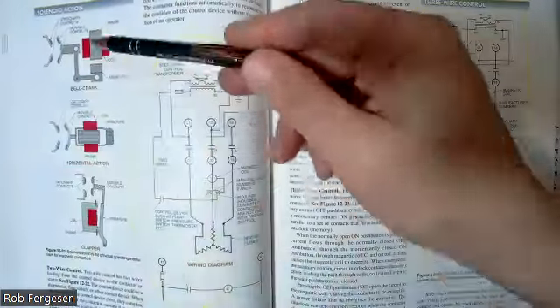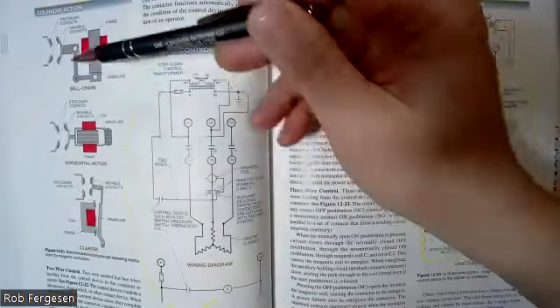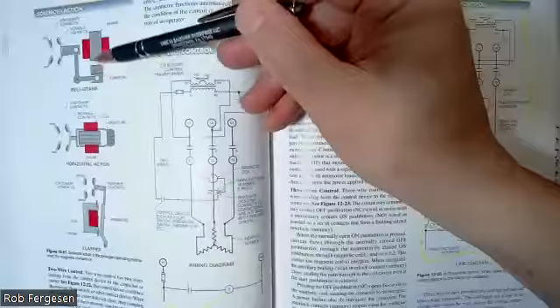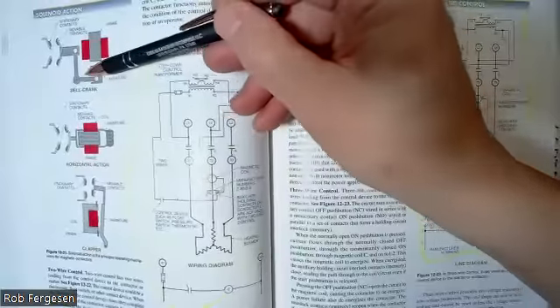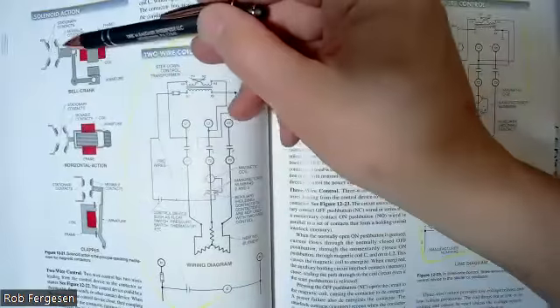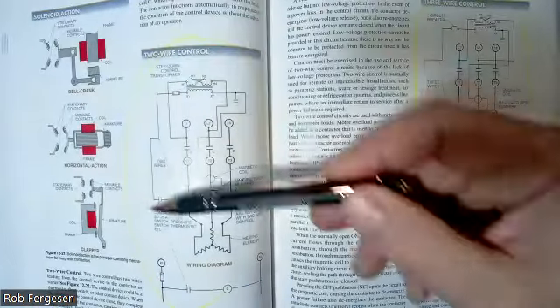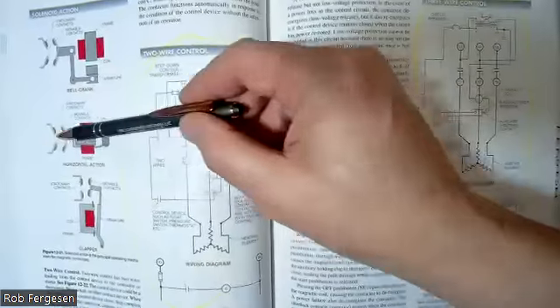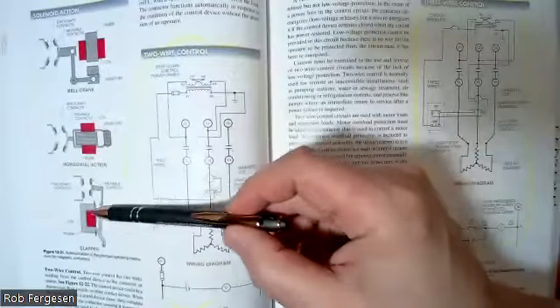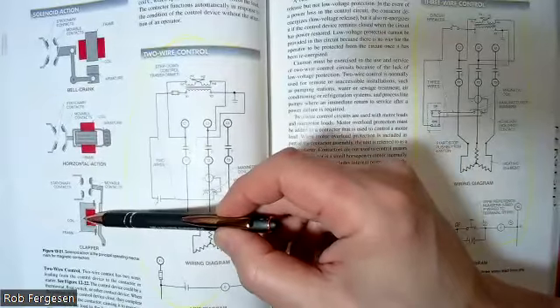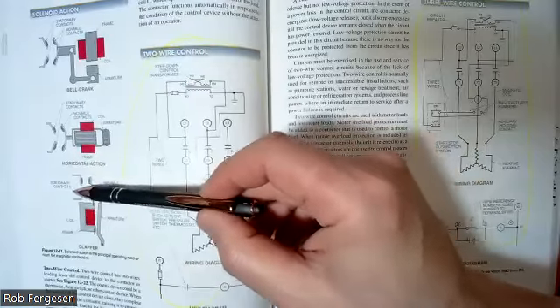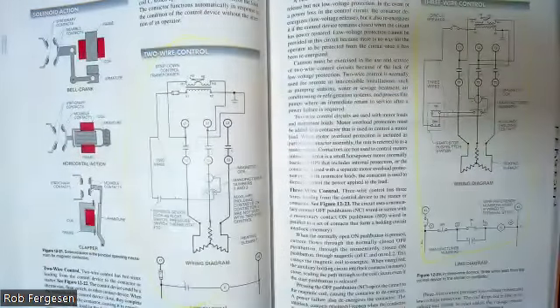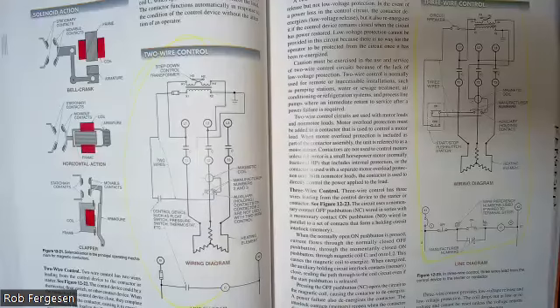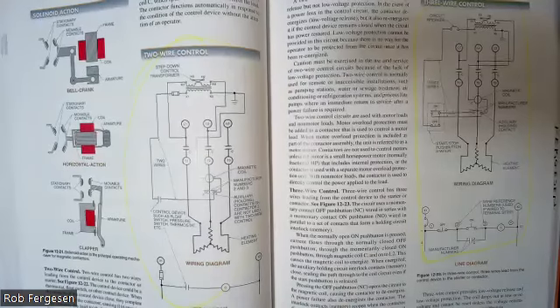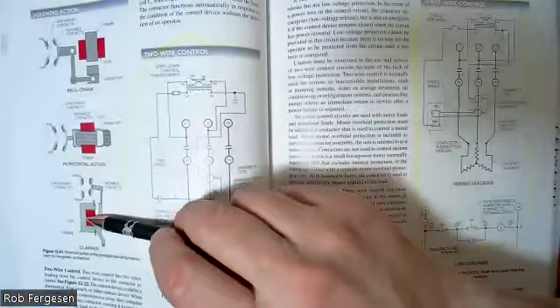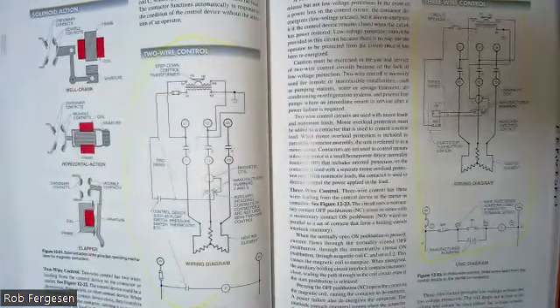But these are three classic configurations for different kinds of contactors, where that coil then pulls together these two pieces, and that rotates this crank, and that pushes back and forth this bar across those two contacts, and so forth here. So this draws it up and draws it down, and this coil here pulls that armature down against the coil, and then pulls that movable contact against the stationary contacts. So these are probably all good terms to use, which I hardly ever use, such as stationary contact, movable contact, coil, frame, and armature. They're pretty classically used.